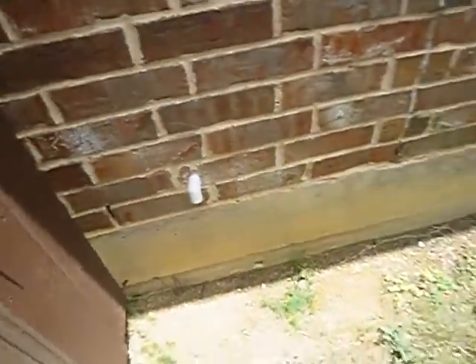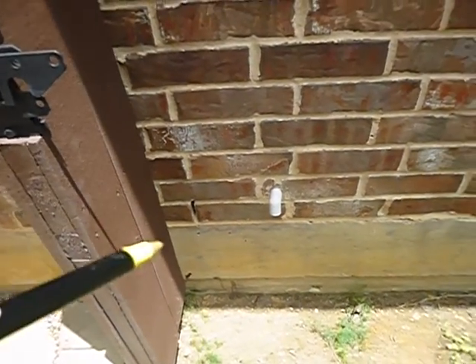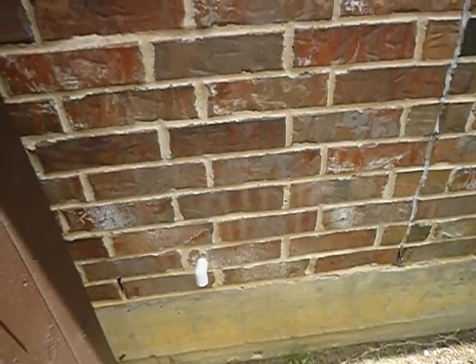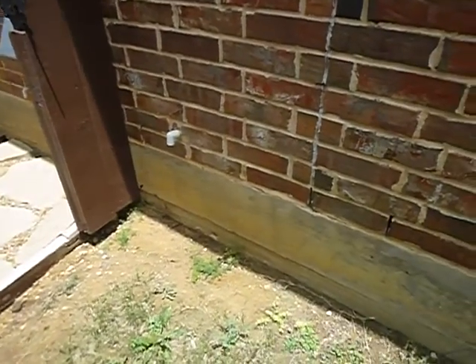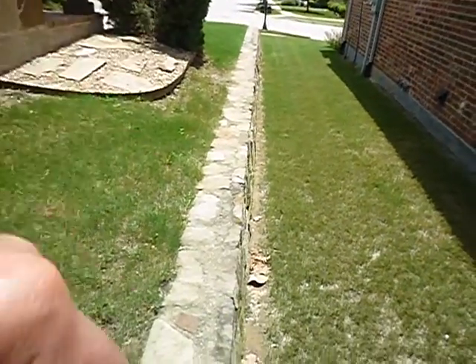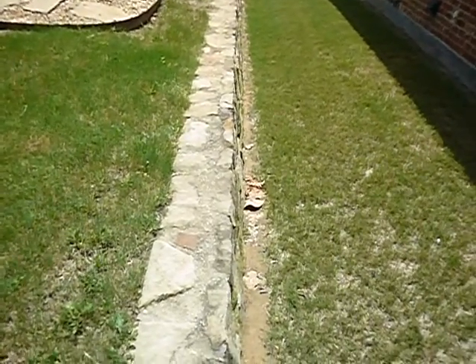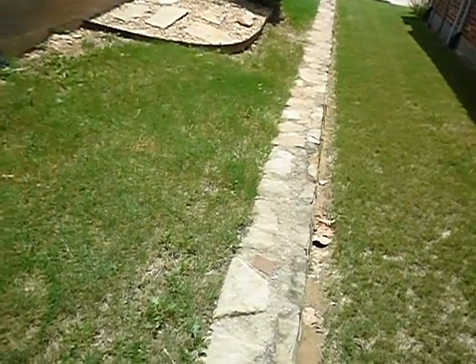And there's another one. So, okay, not a good sign. Because I know the safety pans are commingled. By outward appearances, the temperature pressure relief valve drains are commingled. And what did I just say about that? Yep, that's what I said. You can commingle the pans, but you can't commingle the valves. So there we go. Now, if I'm not just talking out my bobo, then it'd be reasonable to assume this belongs to the inspected house, or if you're my client, your potential new home, and it is more than twice its height away from it.